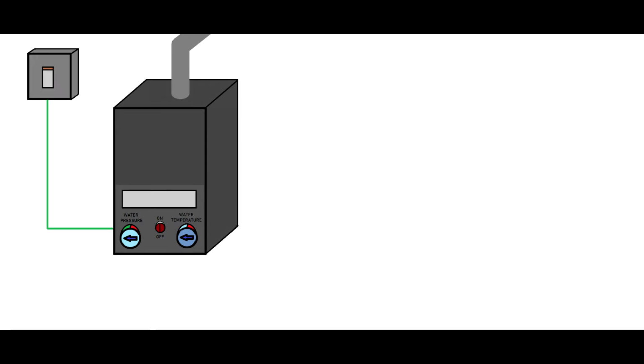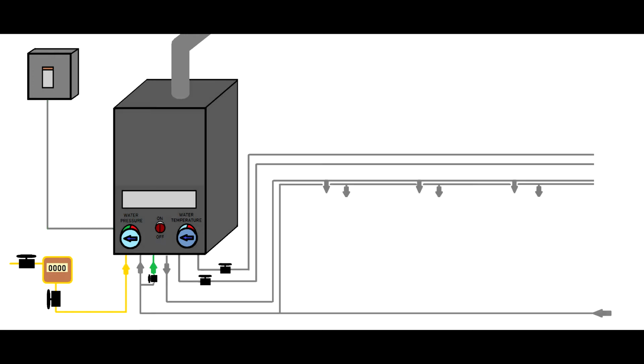So the engineer chooses the boiler and then he will fit the power circuit. Then we have to make sure the gas meter is good enough for our project. Actually, this will be the first thing we do before we even choose a boiler. For the heating agent, obviously we need a highway, so we have to build the pipes. We have to make sure the pipes are thick enough, we have the appropriate pressure, and the design volume will not exceed the expansion vessel's capacity, to secure the elasticity of the system when the water goes from whatever 7, 8, 10 degrees to 70.